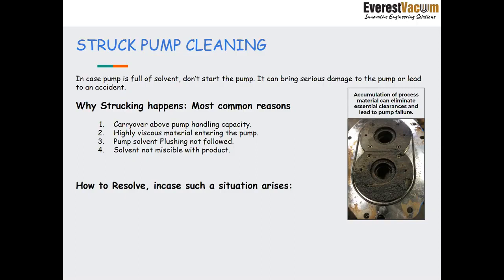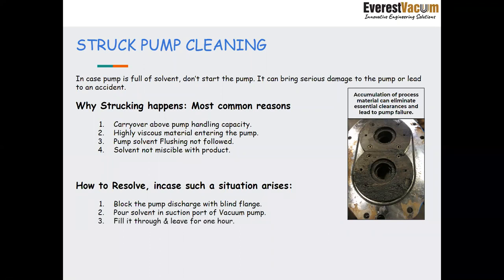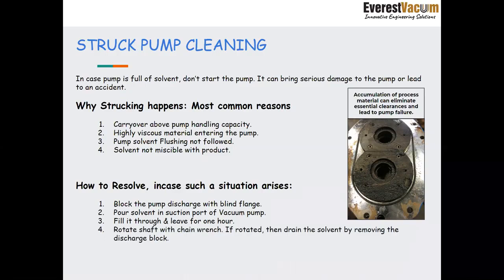So how do we resolve it? If such a condition arises, what do we need to do? In that case, we need to block the pump discharge with a blind flange. We need to pour the solvent into the suction port, fill it thoroughly and leave it for 1 hour. Then we need to rotate the shaft with a chain wrench. If rotated, then drain the solvent by removing the discharge block.